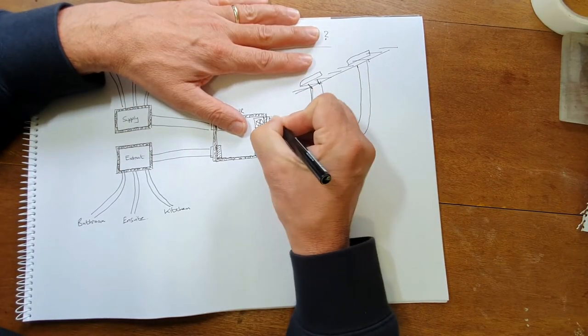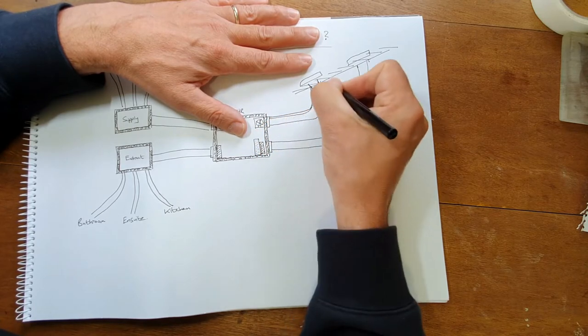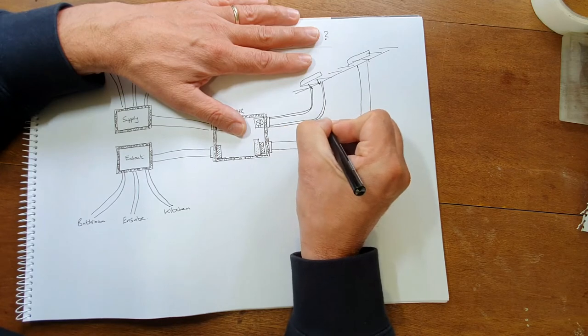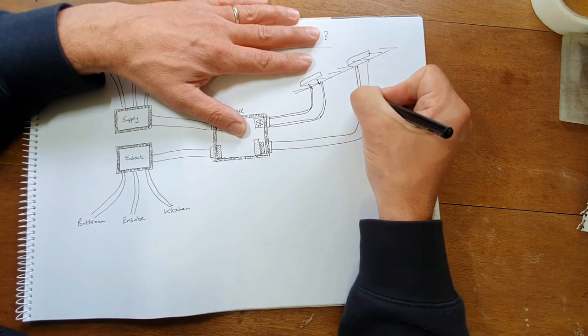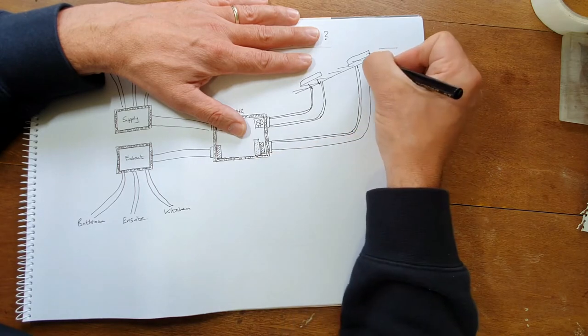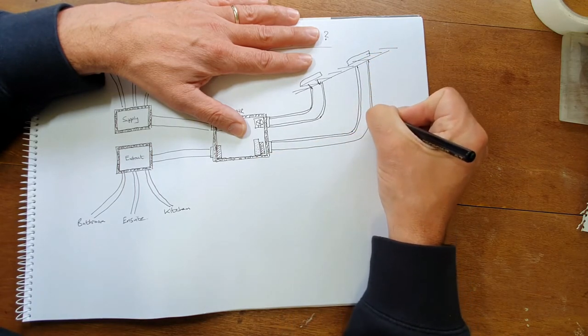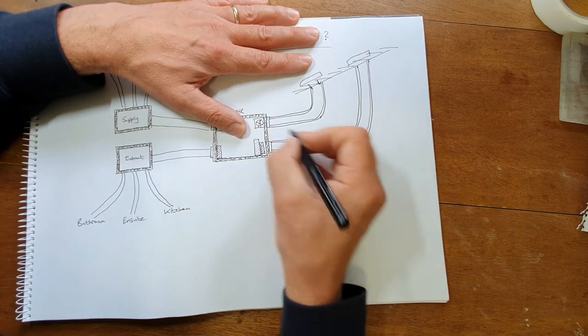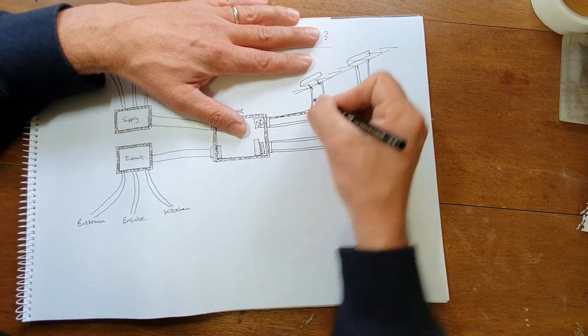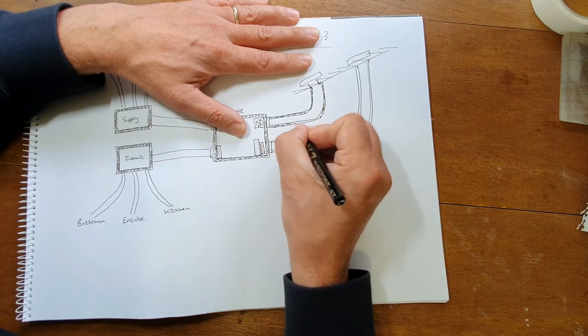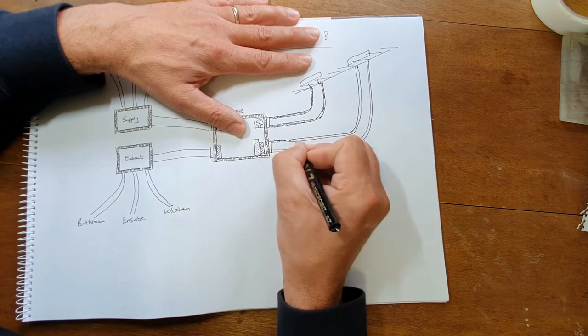This is the duct insulation. It's very important to insulate the ducting that goes between the machine and outside. This is because if you're bringing cold air into a warm space in the middle of winter the outside of the pipe collects condensation quite a lot and that can drip off and drip onto your ceiling and the first you know about it you've got a puddle coming through the ceiling above your head in the living room. So it's very important this is insulated.